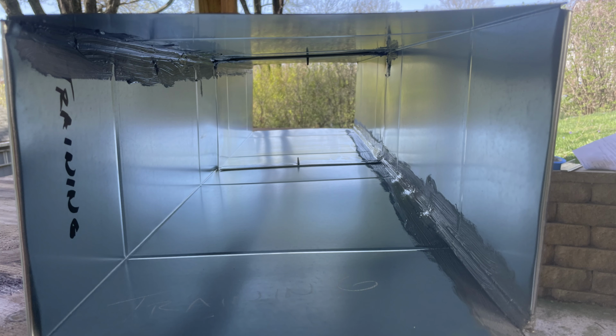When you're ordering your ductwork through the sheet metal shops, there's an option to order it as sealed. A lot of spec jobs will require the longitude seams, the long seams, to be sealed as well. If you order your ductwork sealed from the shop, it'll come out sealed already. If it's not ordered sealed, they're not going to seal it at the shop, and if the specs require it, or if you're getting a pressure test, you're most likely going to have to seal it yourself on site.